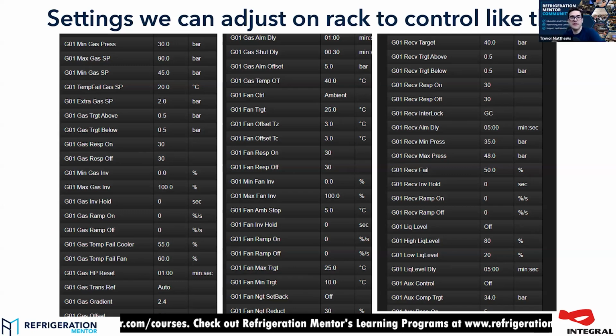Yeah. And if you're listening to this on the podcast and you come and watch the YouTube channel and you see all these parameters, each setup's going to be a little bit different. Like if you've got a spiral CO2 freezer, or a little mini mart or a condensing unit that has some case controllers, versus a supermarket rack. And then you have different sizes of supermarket racks, large ones or small ones. But you've got to go back and watch the other video that me and Kevin did. Go check out the one with Carel and Danfoss, because he showed all the parameters that he uses, but that's his starting point.